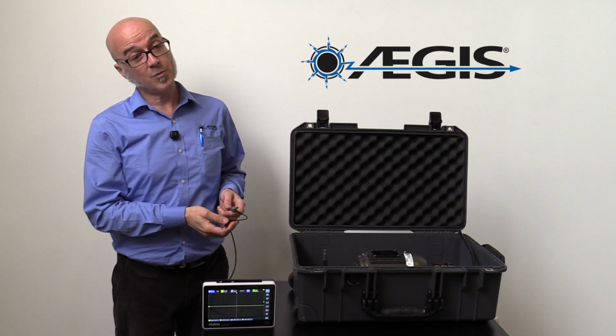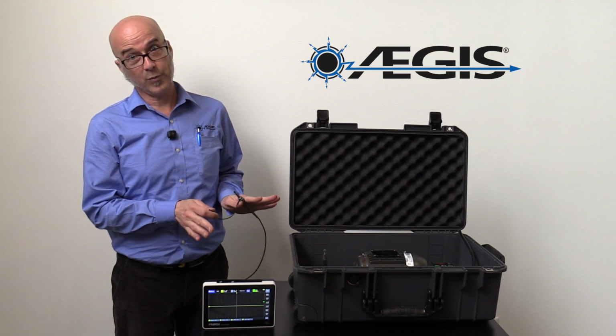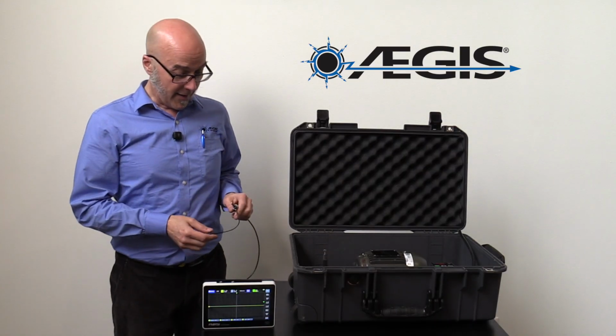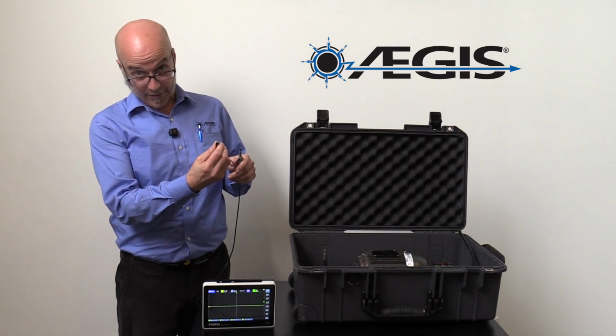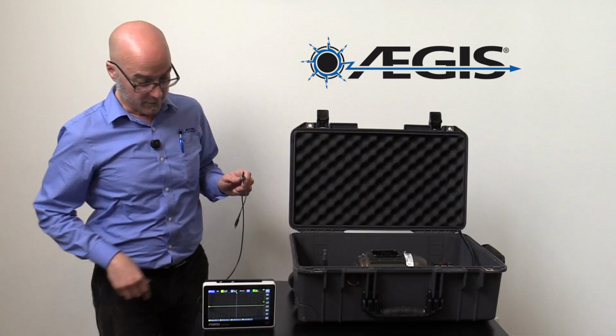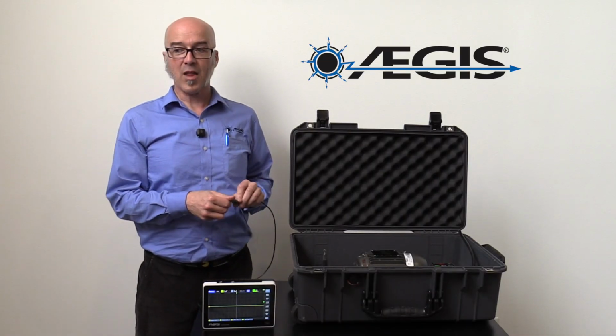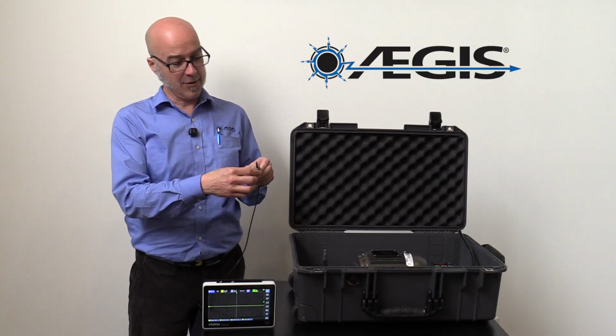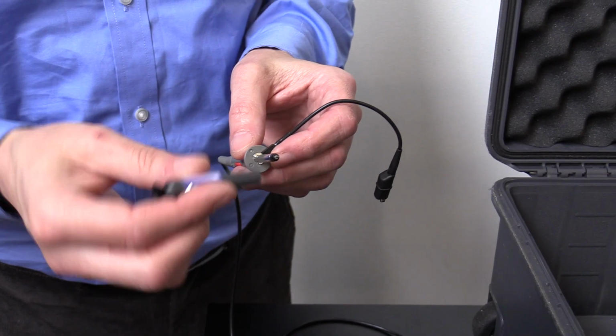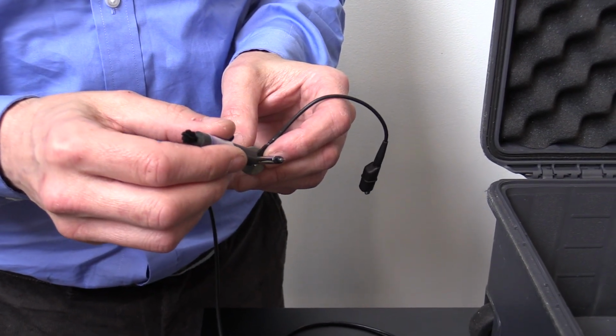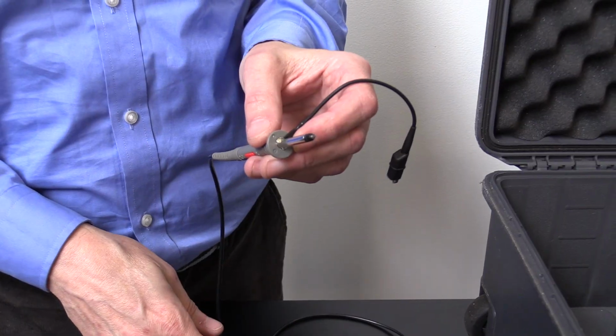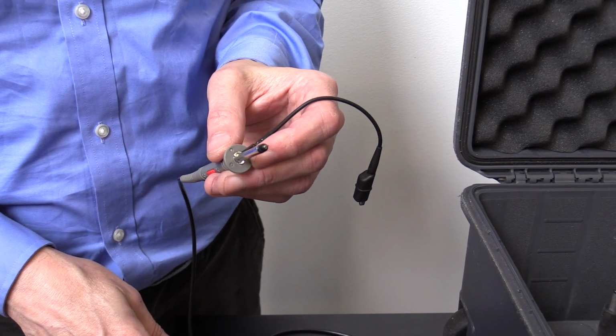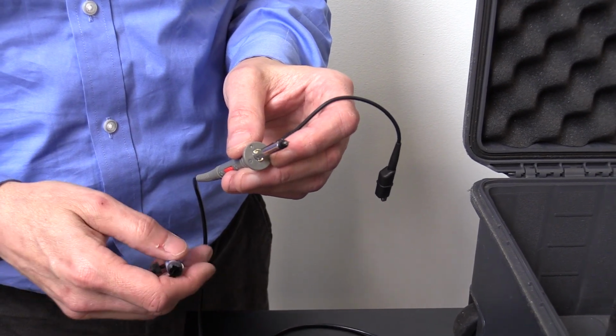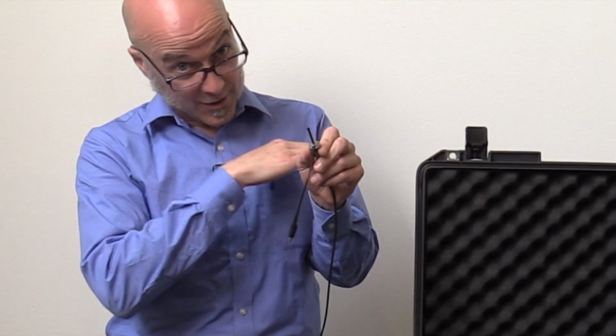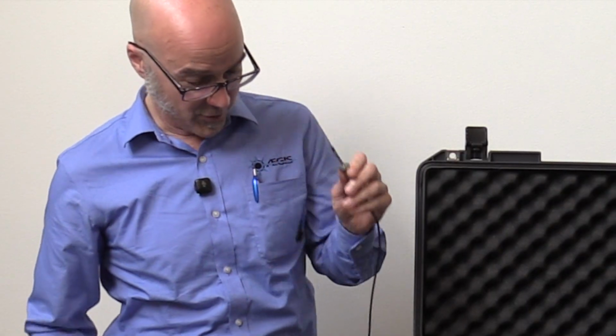Basically, when you measure a voltage, it's always a voltage between two things. So the ground gives you a reference to compare your signal voltage to. So with all of that out of the way, the ground clip is connected to what I call the ground barrel. This is a cylinder of metal that runs up and then it's separated from the tip, which is good because if they came in contact, you would lose your signal and make no measurement.